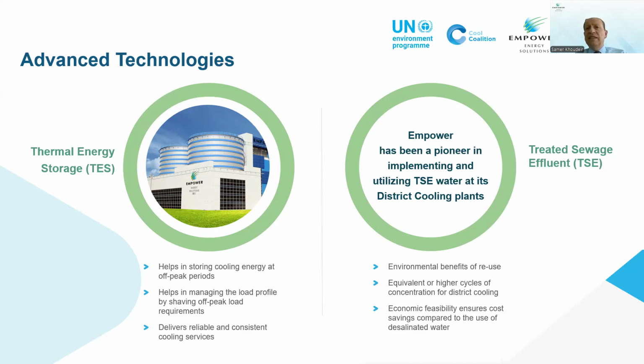Later on, we developed the second generation of these plant rooms where we use thermal energy storage. We have a big diversity between day and night - temperature during the day could reach around 46, but at night we have 35 and 32, so almost 50% of our equipment is not running. So we put a thermal storage tank where we produce the chilled water, and since the peak usually comes from 12 to 5 o'clock in the afternoon, instead of running extra chillers during that time, we open the tank.